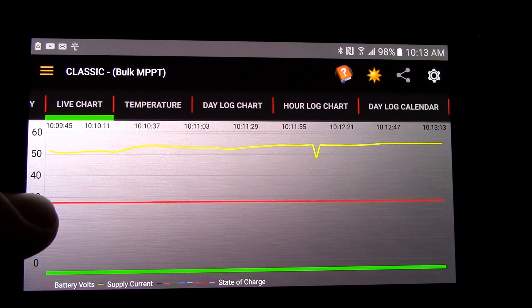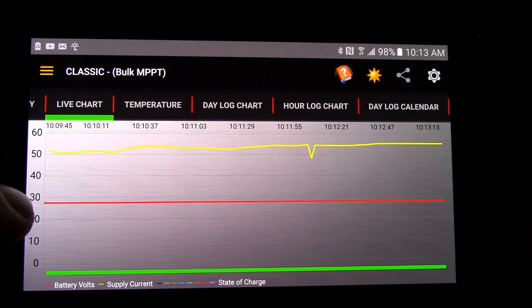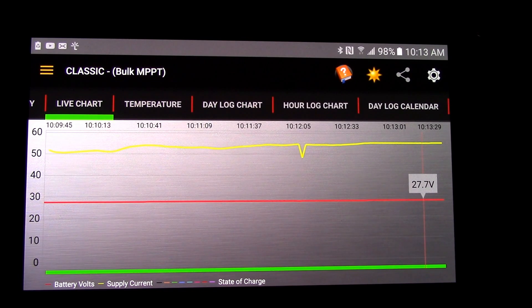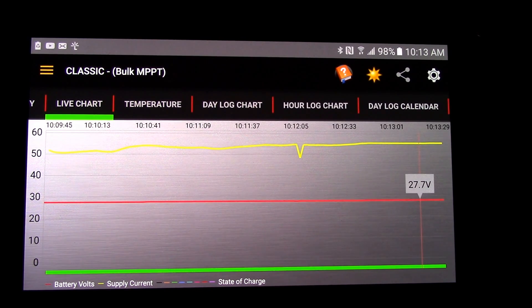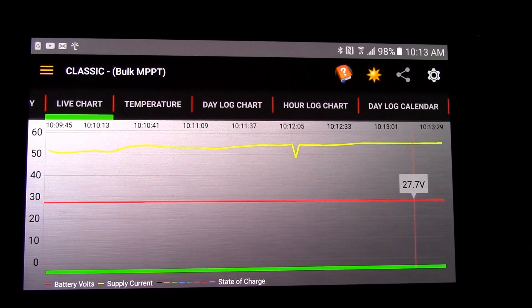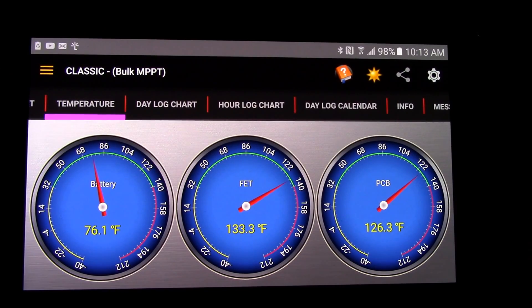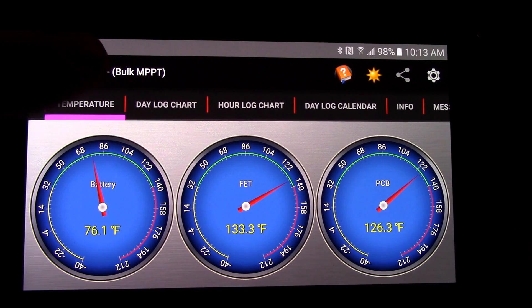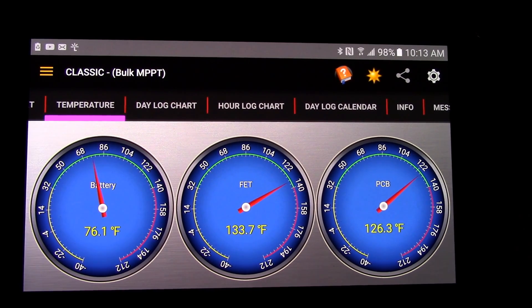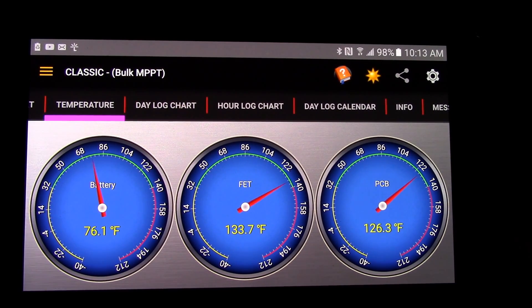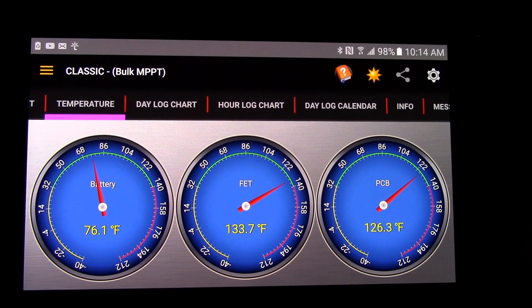This is your battery amps going into the battery, and the voltage is the red line. Let's click on it — it's 27.7 volts. I assumed it was already in absorb but it's not. We've also got temperature readings. It shows MPPT bulk mode. The battery temperature is 76 degrees, which is pretty good. The MOSFET on this circuit board is 133.7 degrees.